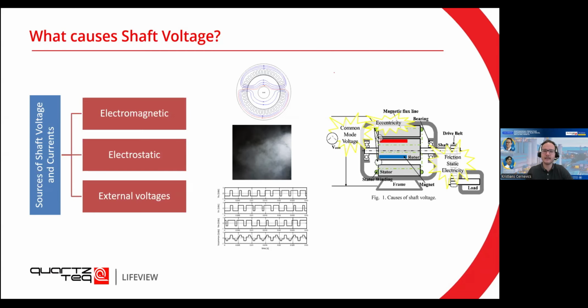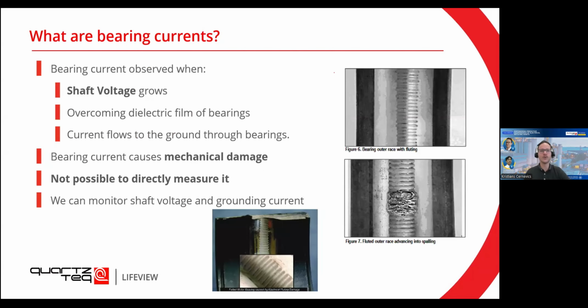So electromagnetic, so maybe some static eccentricity in your machine, some misalignment that puts one part at a higher voltage than the other part. You can also have electrostatic, so a charge buildup through some friction, through some belts, or maybe through some water droplets. And also you can have the external voltages. The question now is, what happens if there is an increased voltage on your shaft? What we're going to observe is bearing currents.